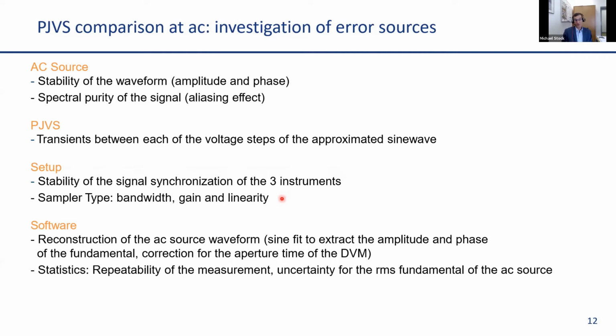And of course, software is important because one needs to reconstruct the AC waveform by fitting a sine wave. And one needs to apply a correction for the aperture time of the DVM because during the measurement time, the signal is not constant. And statistics needs to be done. So we need to determine the repeatability of the measurements and to determine uncertainty for the RMS value of the fundamental of the AC source.